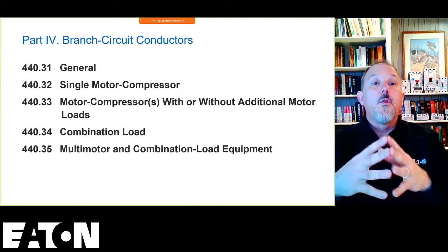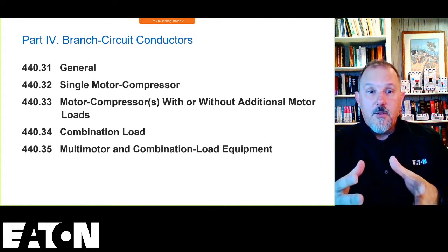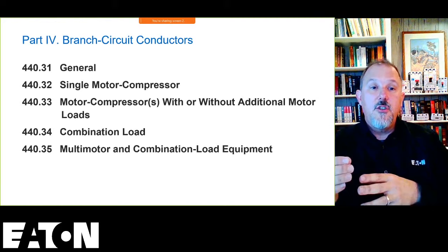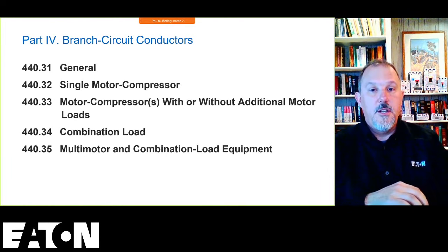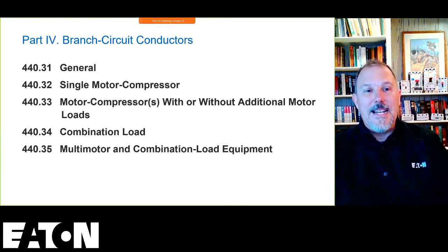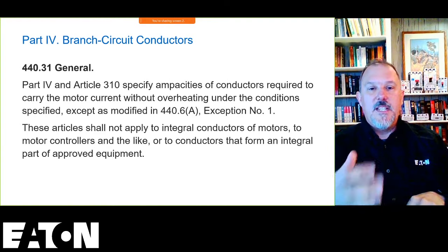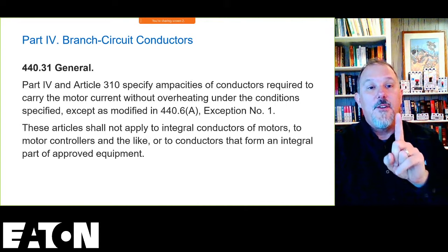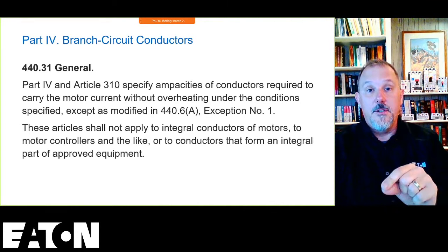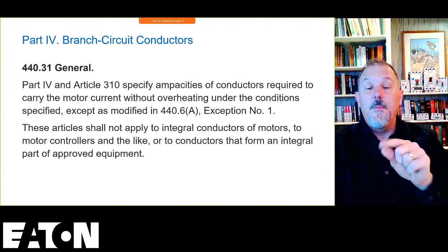Now, if I look at Part 4 in general for branch circuit conductors, 440.31 gives me general requirements. 440.32 talks about single motor-compressors, and then motor-compressors with or without additional motor loads, combination loads, and multimotor and combination-load equipment. If I look at each of those, 440.31 specifies the ampacity of a conductor required to carry. So Part 4 and Article 310 specify the ampacities of conductors required to carry the motor current without overheating under the conditions specified.